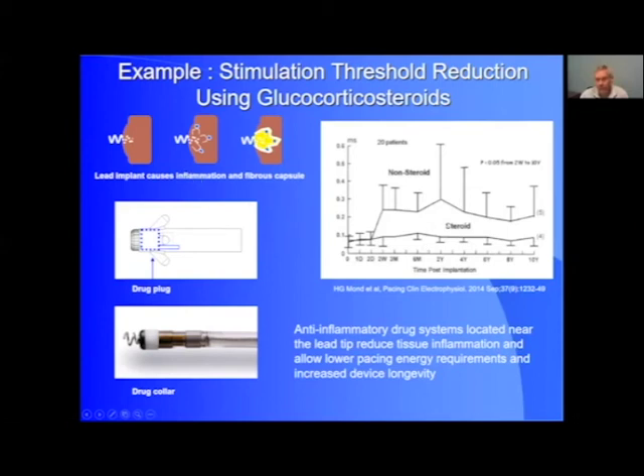And so in the graph to the right, you can see some clinical data where the use of steroids reduced the threshold, the voltage required to provide effective pacing, by several tenths of a volt, which is physiologically and, more important for the life of the battery, very important, and will have an effect on the useful life of the battery. So basically there are a number of different steroid-eluting component designs. There's plugs that can be embedded inside the tip of the pacing lead and provide the drug release, or collars which go around the outside and provide a slow release of steroid.